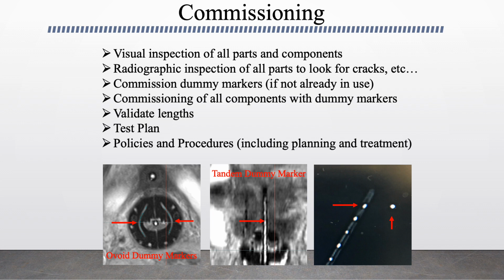The importance of commissioning the applicators before use cannot be overstated. Robust testing should also be performed when moving from CT to MRI-based planning. Variations between the 2 can exist due to differences in the marker used, susceptibility artifacts, etc. Visual inspection of all parts and components should take place, as well as radiographic inspection of all parts to look for cracks. Commissioning of dummy markers and all components with the dummy markers should also be conducted. Validating lengths and running test plans should be included, and policies and procedures should be developed, including both planning and treatment policies and procedures.